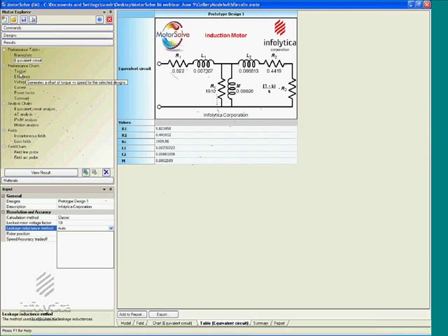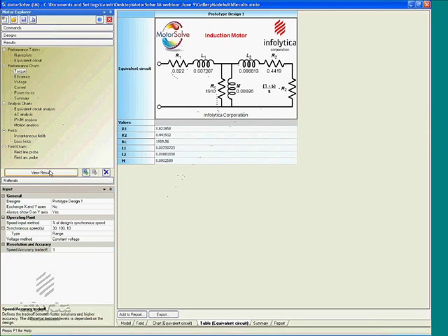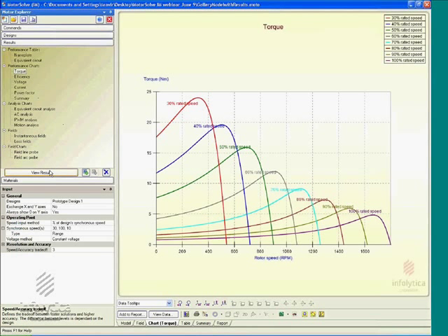It is also possible to generate, having created a model, a performance envelope, if you may say, of torque versus synchronous speed at the fixed slip for any given model. And here you see a series of graphs that tell you the maximum pull out torque that can be achieved from a given model as a function of synchronous speed at a fixed slip, that would be of interest to the machine designer.